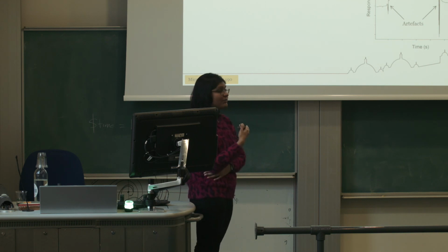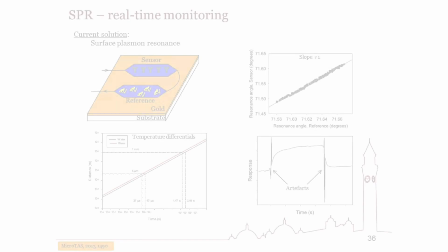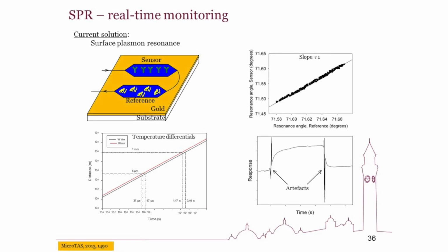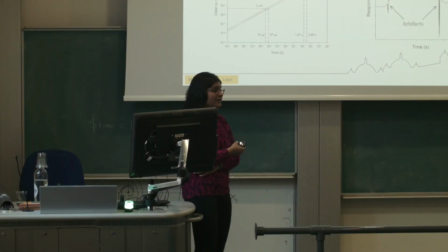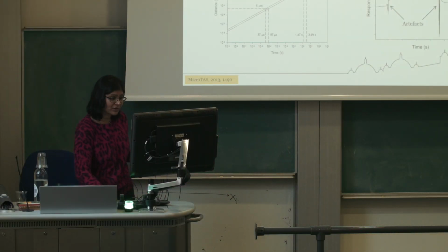And because the solution has to flow from the sensor channel to the reference channel, there is a time delay in the solution to travel, and this causes these kind of artifacts, which makes it difficult to extract the kinetic information. And finally, because the sensor and reference channel are separated in the order of millimeters, it takes about several seconds for temperature differentials to equilibrate. Whereas at the micron scales, it takes tens of microseconds for temperature differentials to equilibrate.